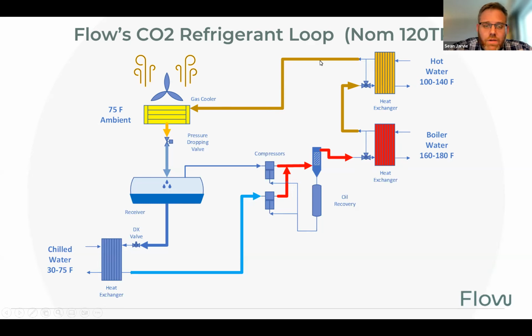If there's any heat left over, it goes to our gas cooler, and we either heat or absorb additional energy that way. Something new with the transcritical system is a pressure reducing valve. This takes that gas that hasn't changed and condensed in the transcritical line and brings it back to a liquid. We do a phase separation in our receivers, so we recompress any vapors and put it right back into the system.